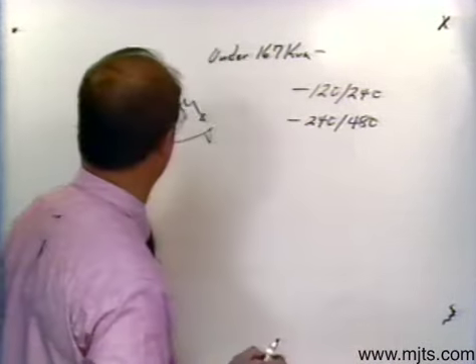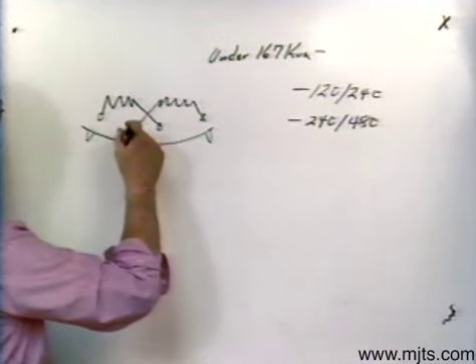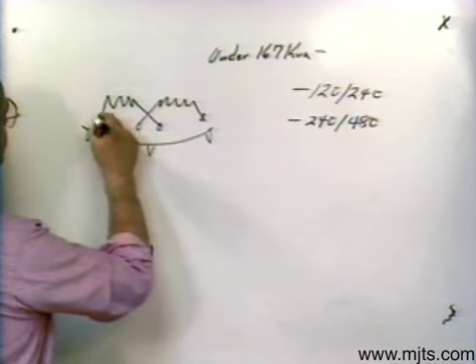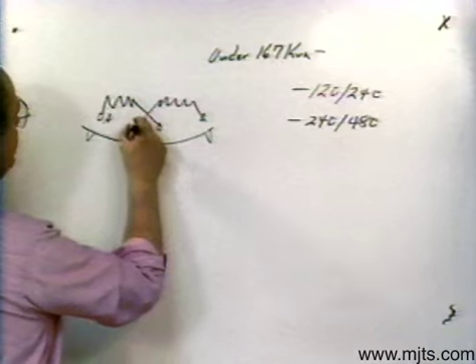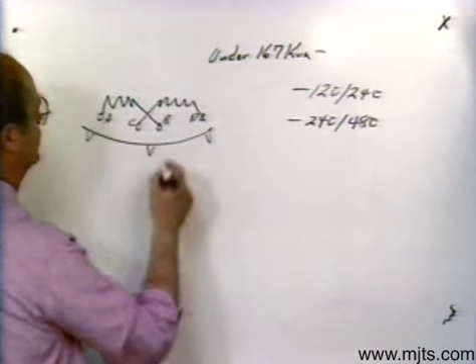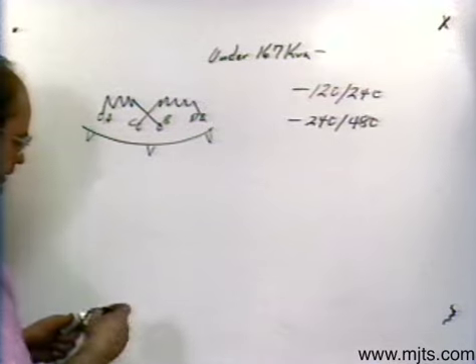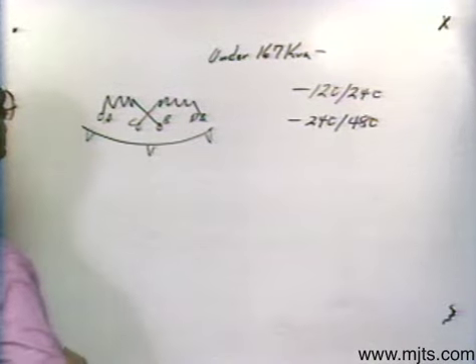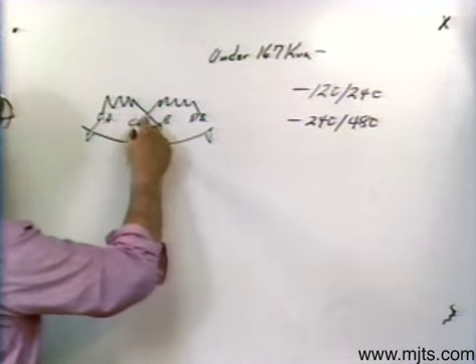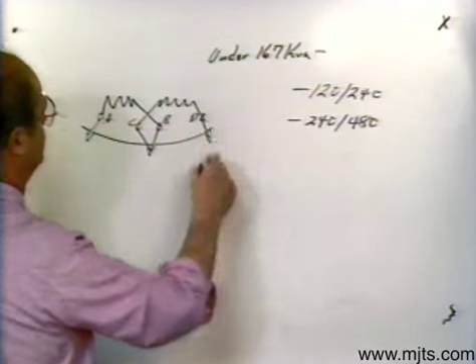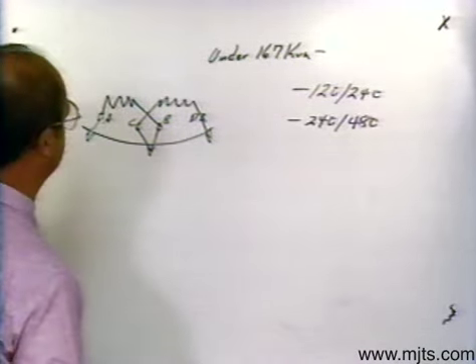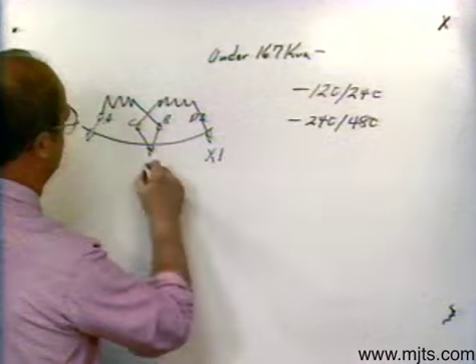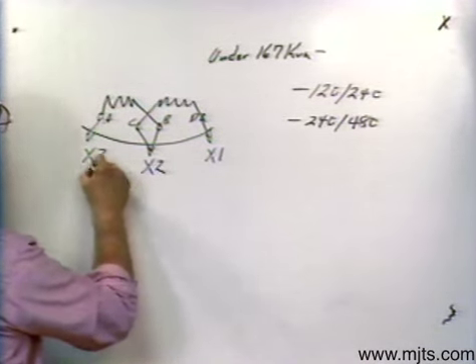The internal connections on transformers under 167 kVA are going to be identified by A, C, B, and D. Normally when it comes to you it's going to be connected series — in other words, A comes out C, and B and D come out. If it's an additive transformer, remember your polarity: that means this terminal is X1, this is X2, and this is X3.